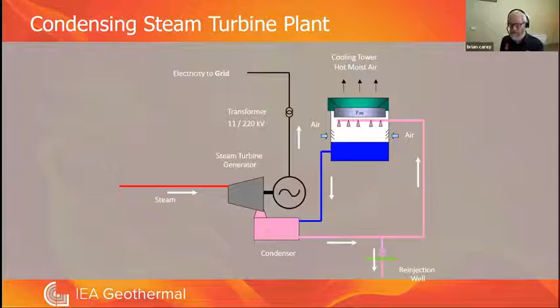And the way you produce fluid for your condenser is that the steam is condensed in the condenser, and that heated fluid is introduced into a cooling tower. The cooling tower cools the fluid, and that fluid is returned to the condenser to go around the cycle again. As you have steam coming in, normally your make-up steam is greater than the evaporation from the cooling tower, so you have surplus condensate to inject. So condensing steam turbines are used really because of effectiveness and efficiency dynamics.